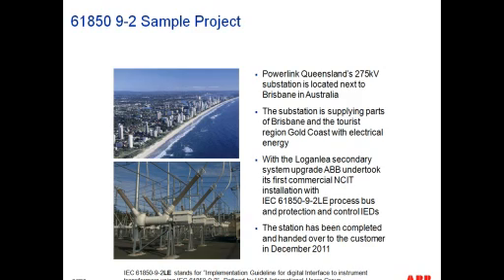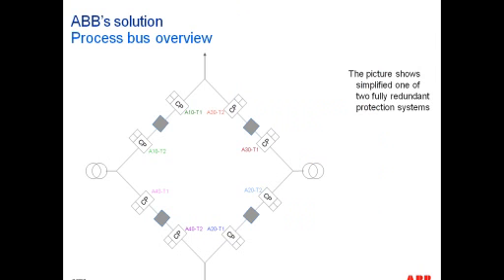Okay, so let's talk about a practical project that ABB just delivered, looking at this from a technical perspective and at the topology of this particular system, so that hopefully some of this information makes a little bit more sense. Essentially, PowerLink, which is a utility in Queensland in Australia, has a 275 kV substation. The idea was to upgrade a ring bus section of that substation with IEC 61850-9-2 LE, so that it would be a process bus installation. This installation was completed and handed over to the customer in December of 2011.